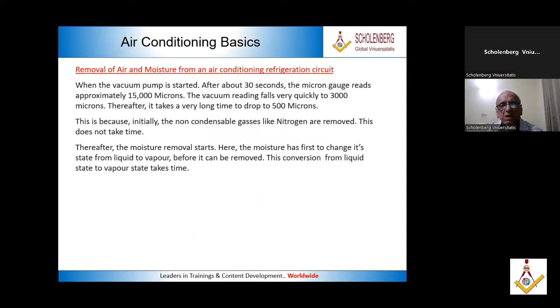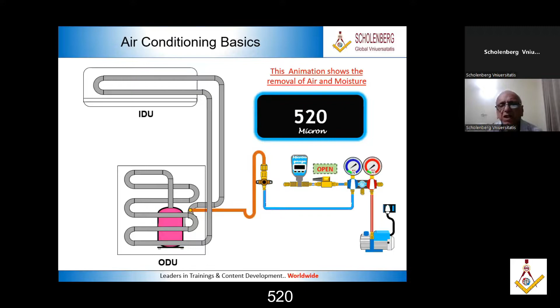Now take a look. This is a setup for the vacuum. The micron gauge readings are coming down, right? This is how the vacuum takes place. From 700 microns, we can take it down up to 500 microns. And we have 530, 520, 510, and stop.